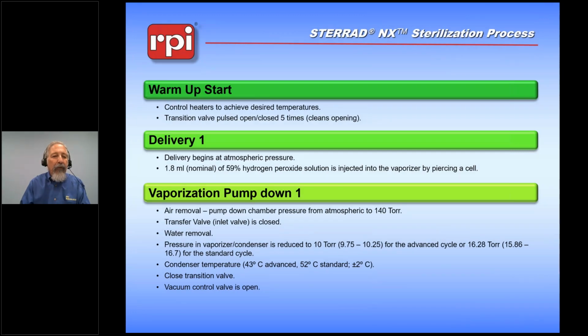Okay, warm up. What does the warm up do? The warm up controls the heaters to achieve the desired temperature, and it allows us to clean the transfer valve. That's a step that will become important later when we move the peroxide. We deliver the hydrogen peroxide into the vaporizer at 59%. We remove the air from the system. We transfer that material into the vaporizer condenser to be condensed.